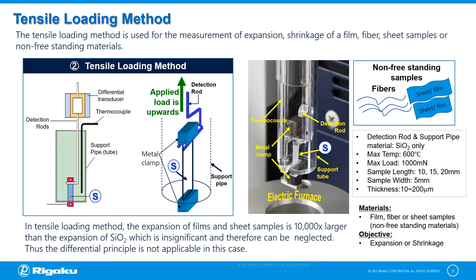The next measurement mode is the tensile loading method, used for the measurement of expansion and shrinkage of a film, fiber, or sheet sample. The detection rod and support pipe are made of quartz, allowing measurements from room temperature up to 600 degrees centigrade, with a sample length of 10 mm, 15 mm, and 20 mm, a sample width of 5 mm, and a thickness of 10 to 200 micrometers. The maximum load that can be applied is 1000 mN.